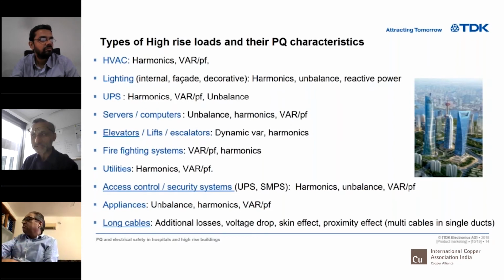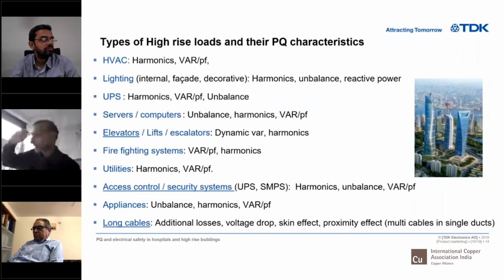And all this lighting is, unfortunately, nonlinear. They create a lot of harmonics, sometimes as much as 70% THD. And since most lighting - I'd say 99% - is single phase, that means they create a lot of unbalance and sequence components.